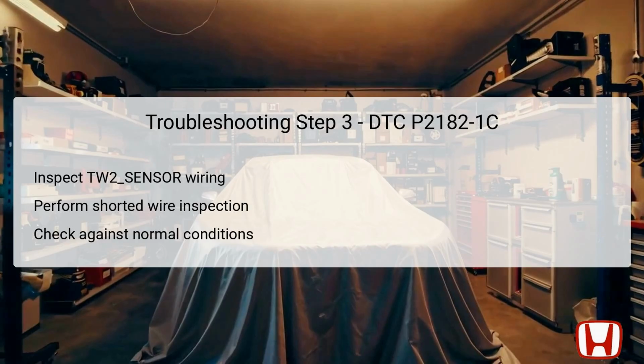This inspection looks for signs of wear that could lead to the sensor being shorted to ground or exhibiting incorrect values. According to the diagnosis procedures, the acceptable norm is more than 1 megaohm of resistance, ensuring that the wiring can carry accurate signals without interference. If there's a fault in this circuit, replacing damaged wiring or connectors will be necessary.